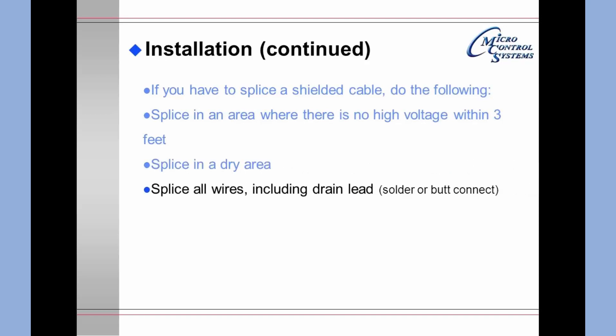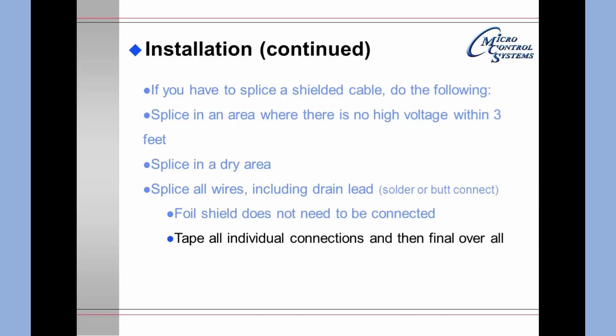Splice in a dry area. Splice all wires including the drain lead. You may solder or butt connect the connections. If you are going to use butt connectors, stagger the wiring so that all of them do not end up in exactly the same spot. The foil shield does not need to be connected. You will tape all individual connections and then tape over the final splice.